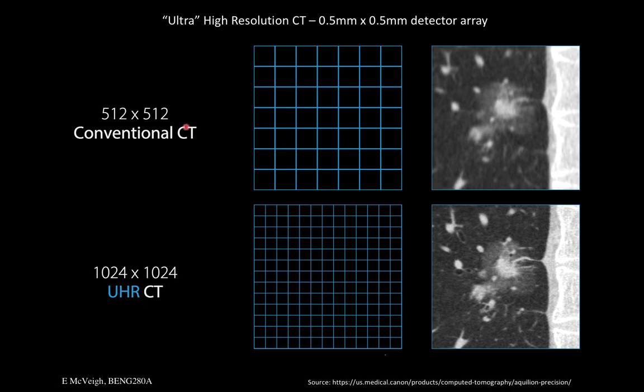Okay, since this is apropos for today, since we talked about sampling, there is a manufacturer who has taken their normal two-dimensional detector array, which in their case is 320 by 1,000, right? And they've said, well, let's just go to 640 by 2,000. Well, actually, what they did was they cut the thing down. And so they essentially doubled the resolution in two directions, in the z direction and in the theta direction, or along L, right?